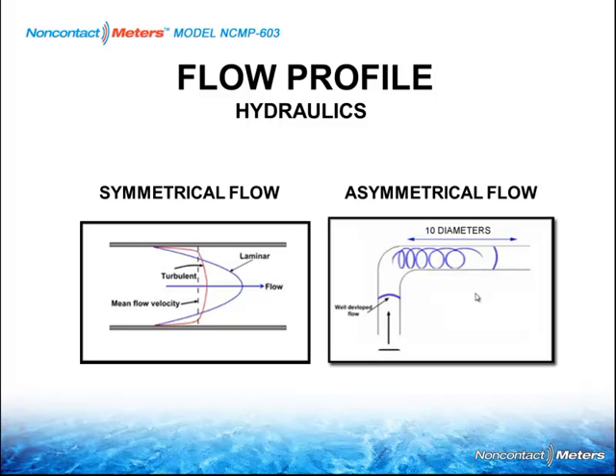Now the opposite of that would be this, an asymmetrical flow profile, where you have an elbow in an application, and my flow is going up this elbow here, and you notice this distance is shorter and this distance is longer. And you're going to get a tumbling effect right here after the 90. If you were to put your transit time flow meter here, you're very likely to get no data as opposed to erroneous data. Go down 10 pipe diameters, plop your sensor there, have another 5 on the other side, and you're good to go.